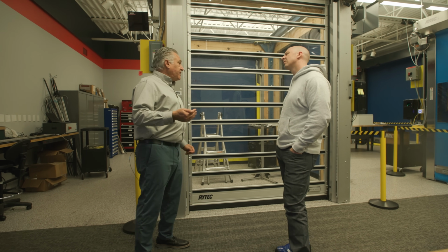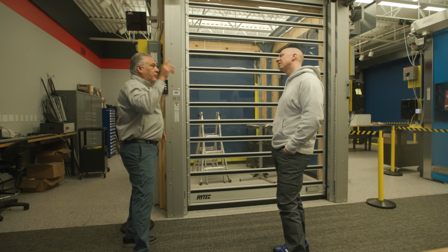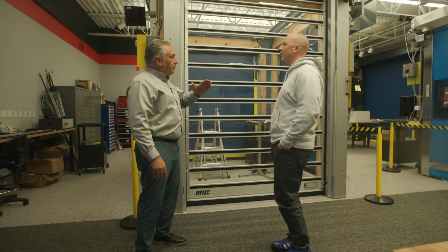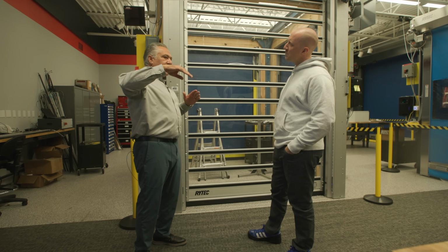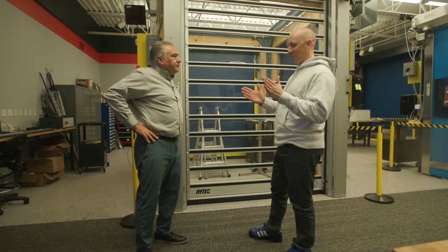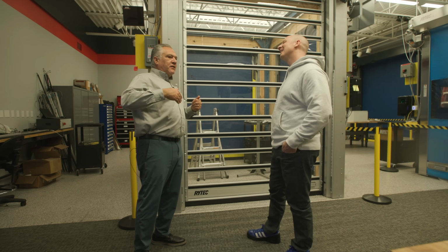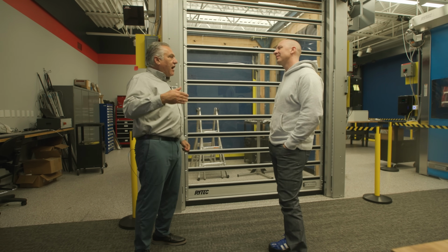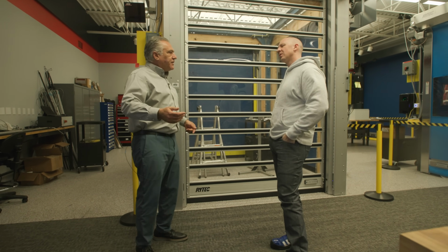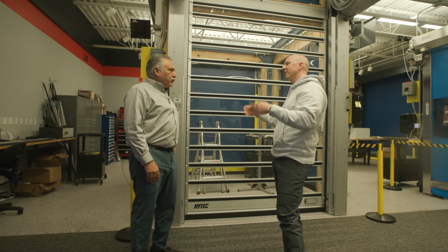It has an up to speed that's a little bit higher, because the 80 inches a second, when we drive this door and we move it, we actually go through what we call a speed profile, where it goes through an acceleration curve. And then it gets to maximum speed, and then before it gets to the end position, it starts slowing down and stepping down. Correct. The algorithm says you have so much distance or time to slow down, and it maximizes that so that it spends as much time at high speed. So your curve looks like this, and then as it gets to the end, it has to slow down a little bit. Correct.